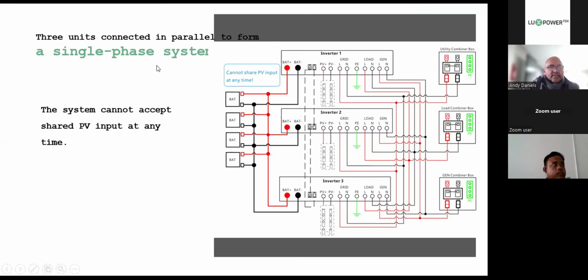Okay, here, this drawing looks quite imposing, but it's not really. This is just 3 inverters connected in parallel to form a single-phase inverter system. So here you have inverter 1, here you have inverter 2, there's inverter 3, and here is a shared battery bank, right? And then you have your PV, and here I see Kathy's put it in blue. Remind you guys, you cannot share PV input anytime, okay? Batteries you can share across a common DC bus, but PV cannot be shared under any circumstances. Right? Don't try it.